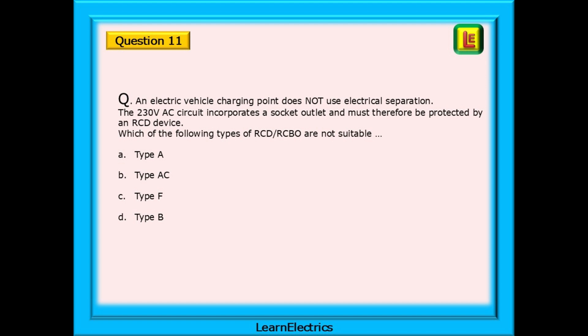For question 11, we have an electric vehicle charging point that does not use electrical separation. The 230 volt AC circuit incorporates a socket outlet and must therefore be protected by an RCD device. Which of the following types of RCD, RCBO are not suitable? Pause the video and find an answer.